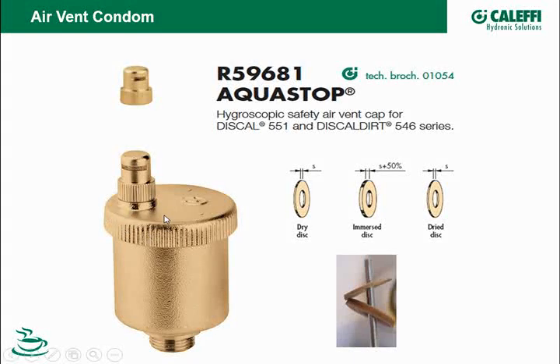So if some dirt or debris gets stuck in this little stem that the float moves up and down to shut the air off, and it leaks through, now you've got the cap that'll catch it. Within about 2 to 3 seconds of these fiber discs getting wet, they'll swell up and shut this cap off. And then of course as the water goes away, they dry out and they can allow the air to come out again. So I would definitely put these on critical applications, like if you're going to put a radiant manifold up in somebody's closet or something where you don't want the water getting out on their floor. This is a good way to give you another level of protection.